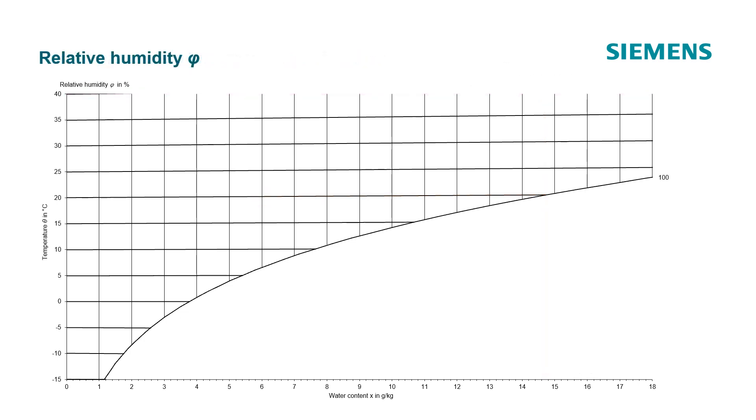Relative humidity: Along the saturation line, the air is saturated with 100% of water vapor. This air state is also referred to as 100% relative humidity. In the same manner, lines with other percentages of constant relative humidity exist. For example at 40% relative humidity, air states on this line each show a water vapor content being 40% of the saturation state.